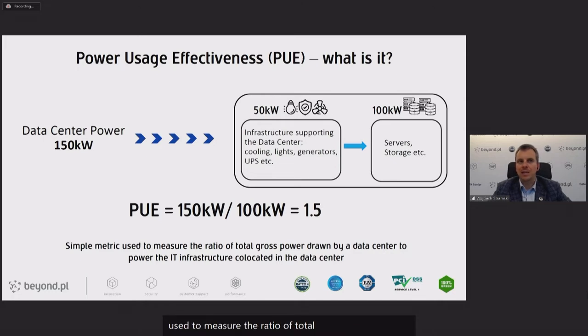For a very easy and simple illustration, if servers and storage equipment require 100 kilowatts to be powered, then the question is how much additional energy is required to power the supporting infrastructure of that data center: the cooling equipment, the lighting, the generators, the UPSs, the security infrastructure. In this very simple example, if 100 kilowatts is drawn by servers and storage, and another 50 kilowatts to power the supporting infrastructure...